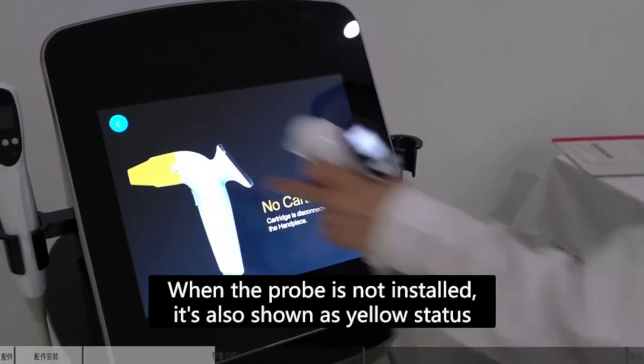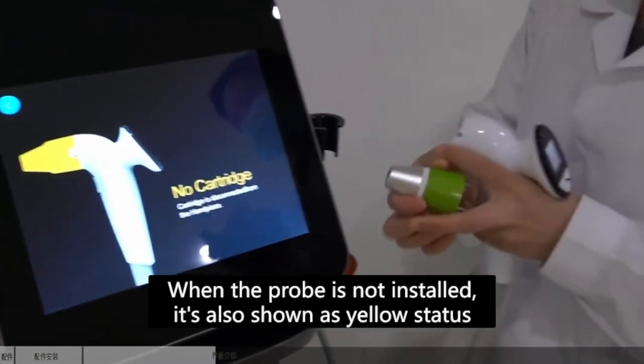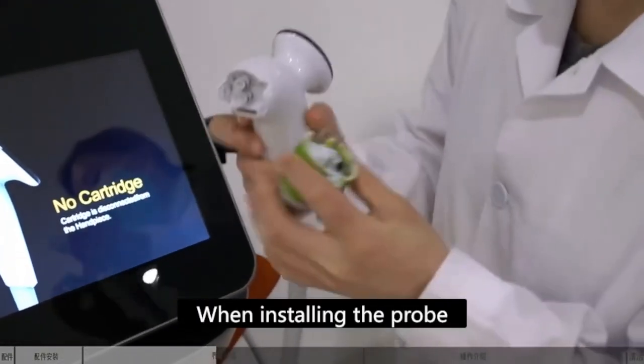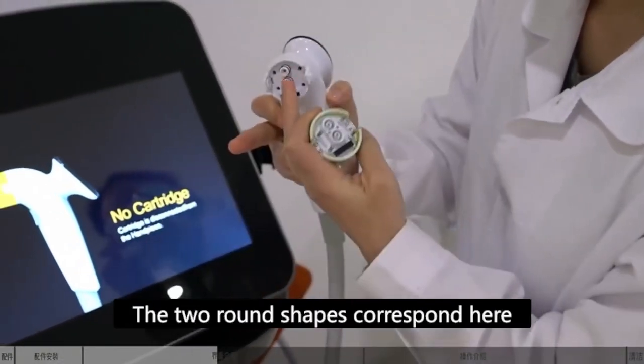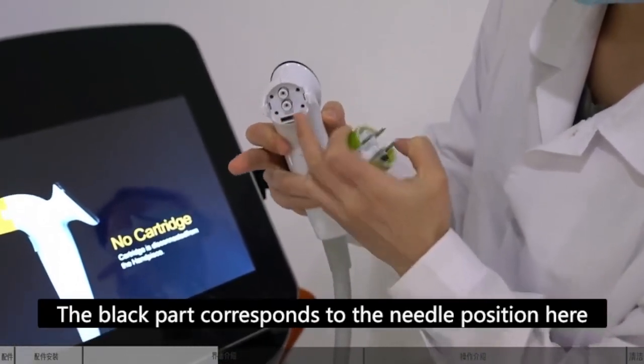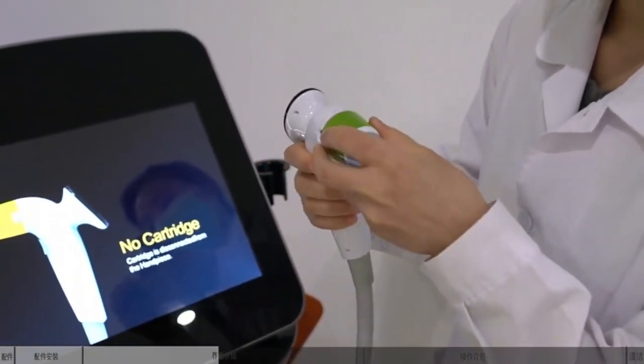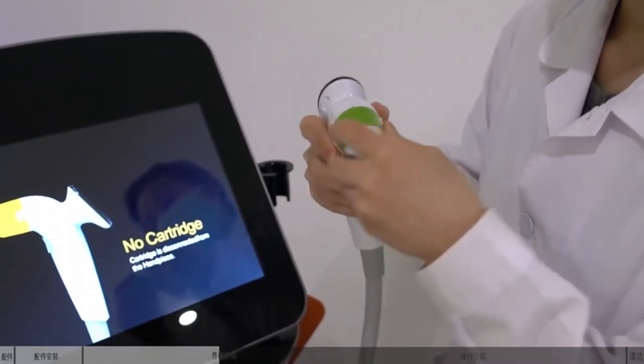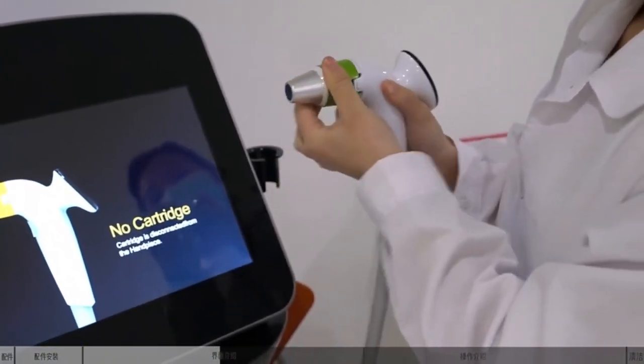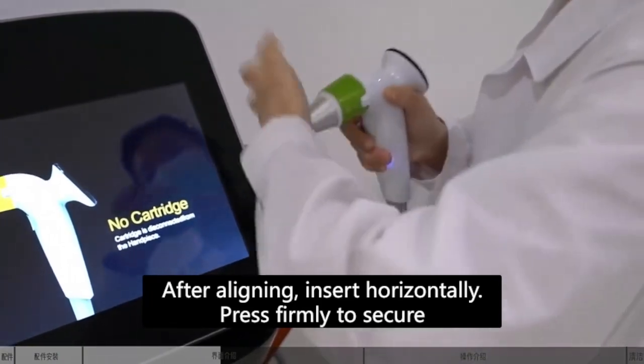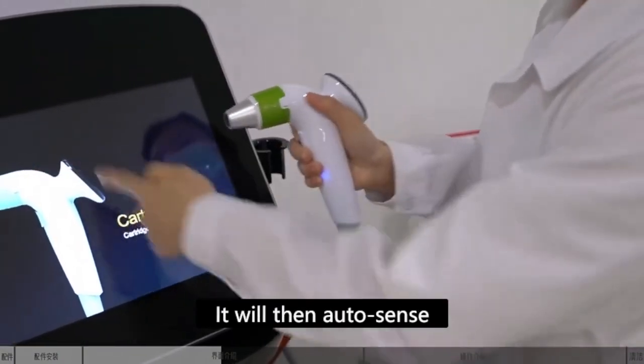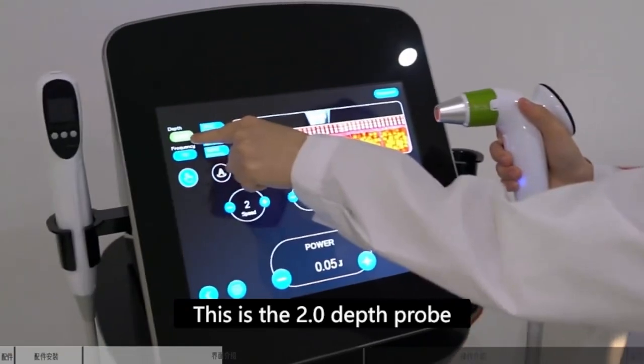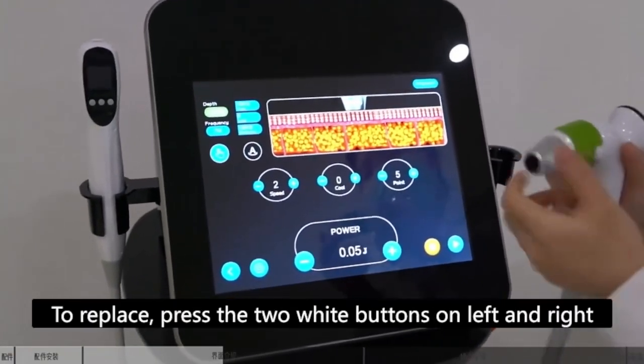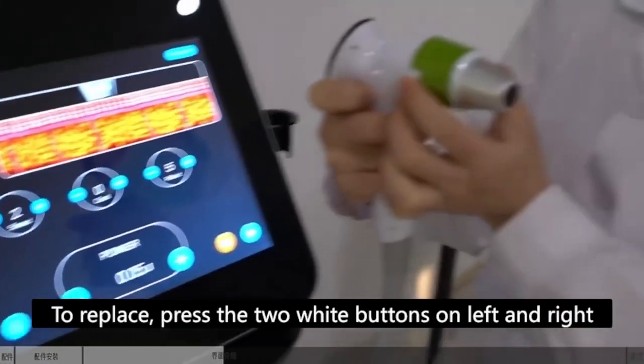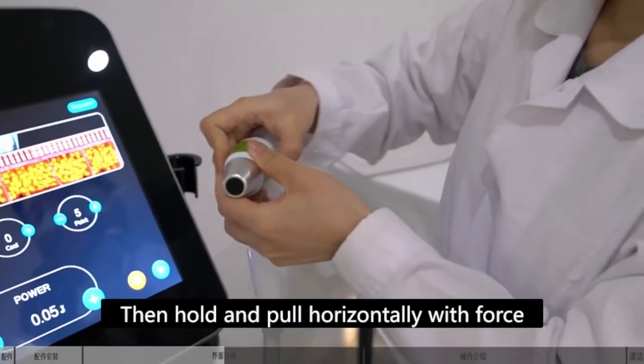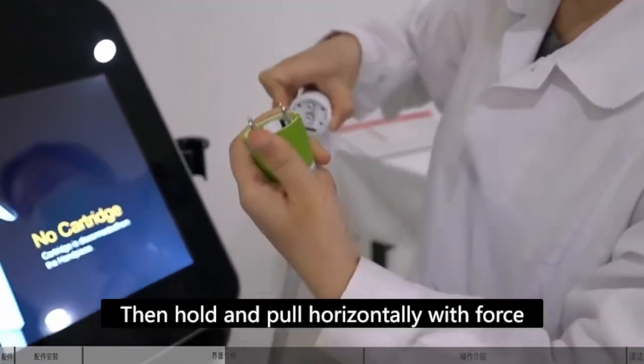When the probe is not installed, it's also shown as yellow status. When installing the probe, the two round shapes correspond here. The black part corresponds to the needle position here. After aligning, insert horizontally. Press firmly to secure. It will then auto-sense. This is the 2.0 depth probe. To replace, press the two white buttons on left and right. Then hold and pull horizontally with force.